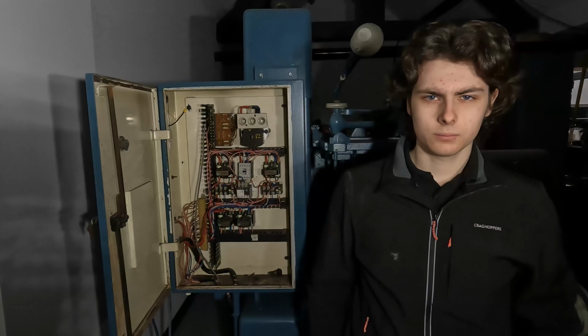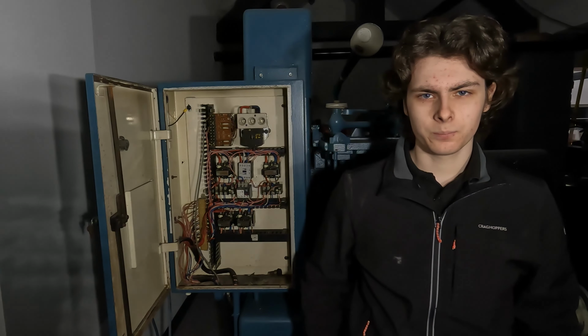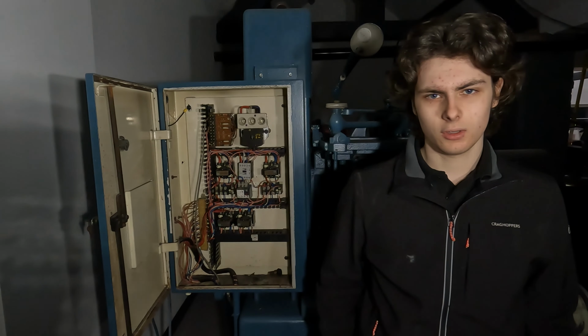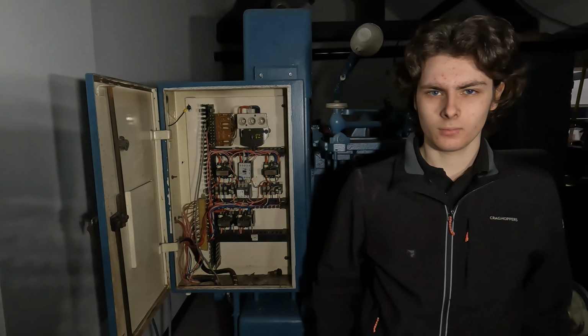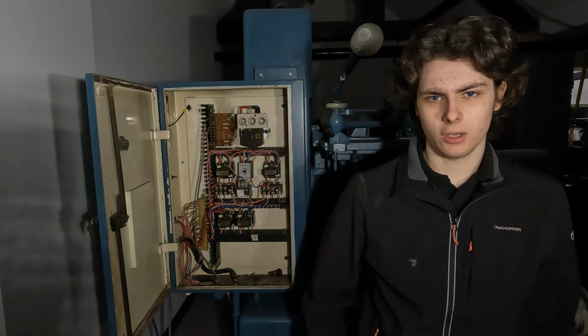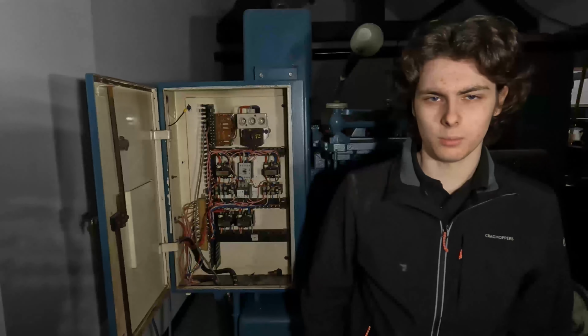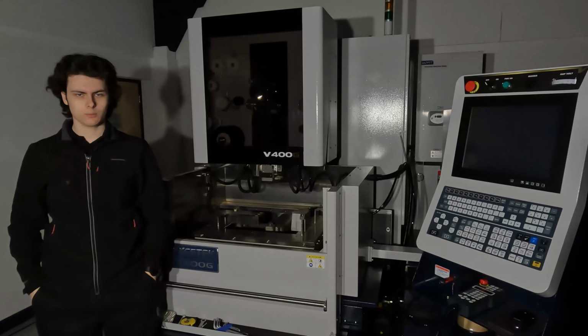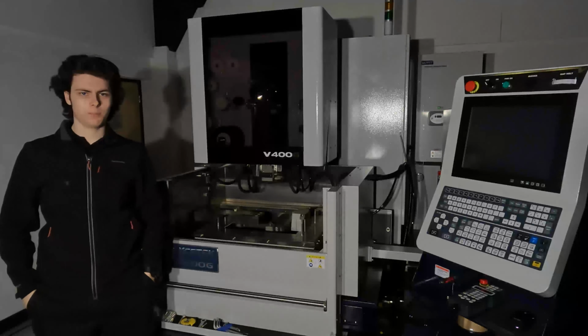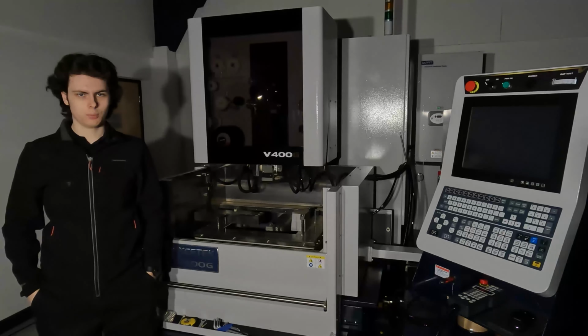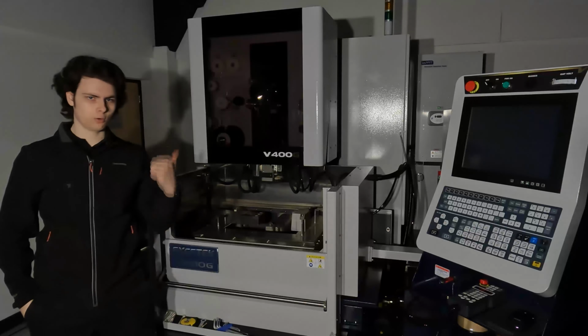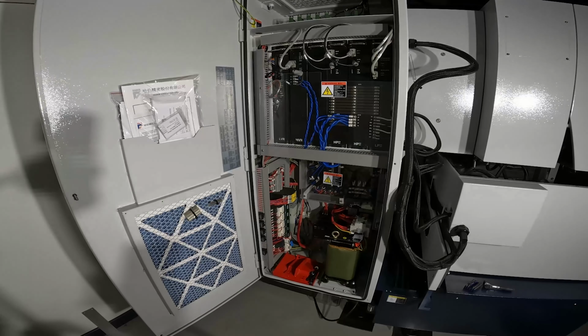this machine. You can immediately see this electrical cabin behind me has no electrical sensitive devices, control circuitry, or anything of that nature. Instead, it just has basic contactors, transformers, motors, that type of thing. This is not a problem if you want to run this type of machine. Many machines like that one will work without a problem, but where power quality is critical, you need some additional components to clean up the signal, so to speak, like for this wire erosion machine behind me. You can immediately see the contrast between these two machine tools and how they function. There are a multitude of control electronics, inverters, drives, and process monitoring circuits in here which are referenced to ground and require a high quality of power to function without breaking down.